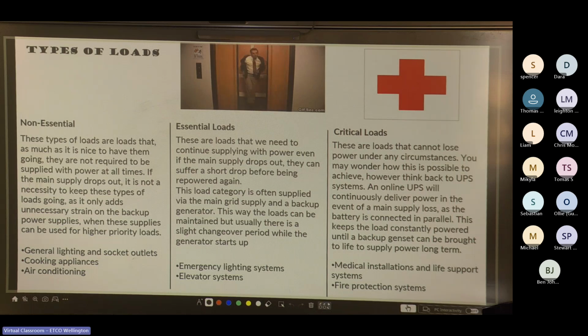Cool. So you got your different types of loads. So your non-essential loads. The loads are just that. It's nice to have, but you're not going to require them. You know, if you have them, don't have them on, it's an inconvenience, but it's not going to cause you any ill effect. So it's not a necessity to keep these loads going. It only adds unnecessary strain on the backup power supplies, when these supplies can be used for higher priority loads, so things like general lighting and socket outlets, your cooking appliances, or your air conditioning. Although some of us would argue in the height of summer, air conditioning is definitely essential.